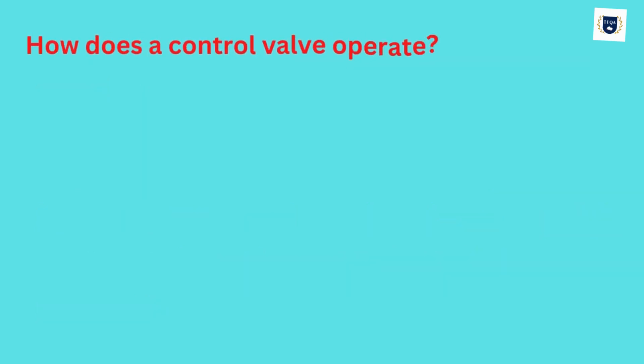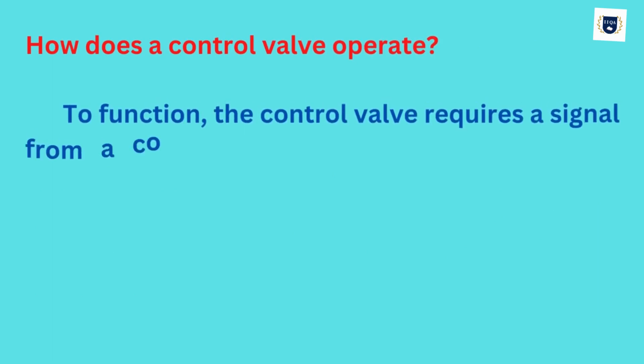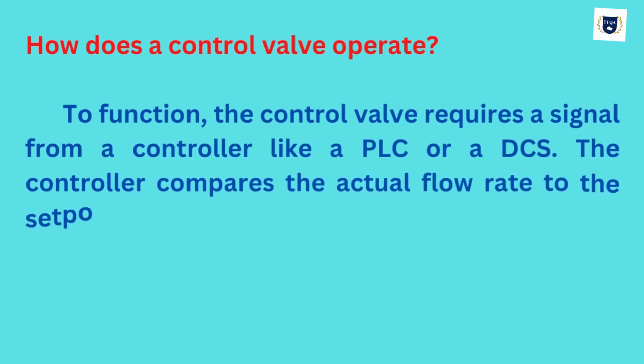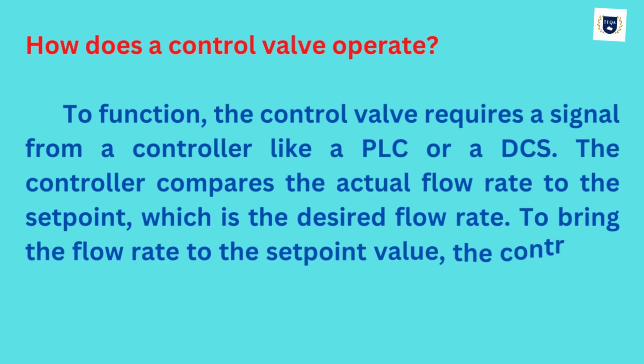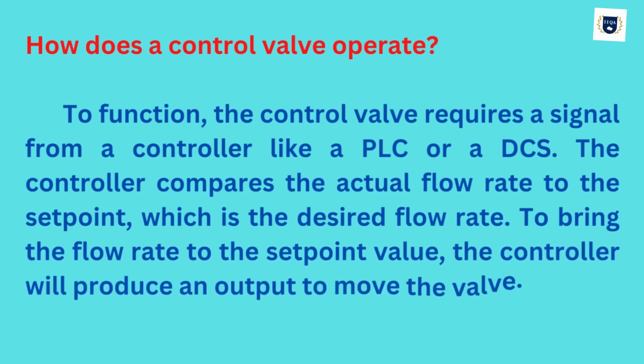How does a control valve operate? To function, the control valve requires a signal from a controller like a PLC or a DCS. The controller compares the actual flow rate to the setpoint, which is the desired flow rate. To bring the flow rate to the setpoint value, the controller will produce an output to move the valve.